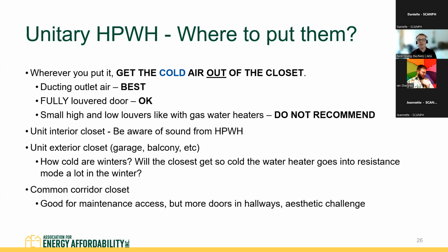So, other things to be aware of. If you put it in an interior closet inside of an apartment, be aware of sound, right? Heat pumps have compressors, they have fans, they have sound ratings, and you can get quieter units, but they're not silent. So be aware of where you're putting it.